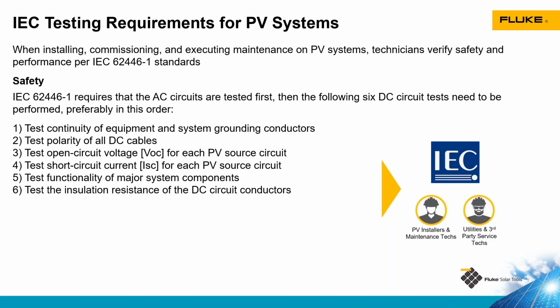In the standard, there are two main categories of tests. The category 1 tests are safety tests. This includes checking the continuity of our equipment ground, so making sure our non-current carrying metal parts like module frames, racking, conduit, junction boxes, and disconnects are all electrically connected together. We also test polarity, open circuit voltage, and short circuit current of our DC circuits.